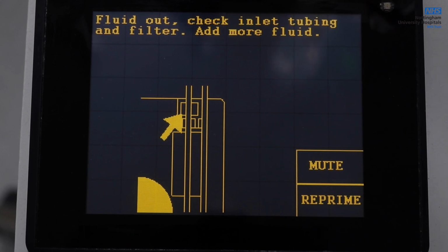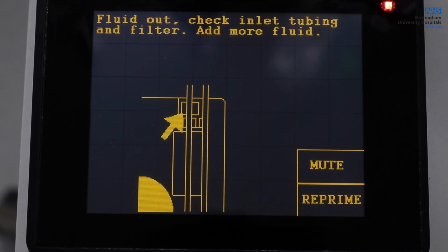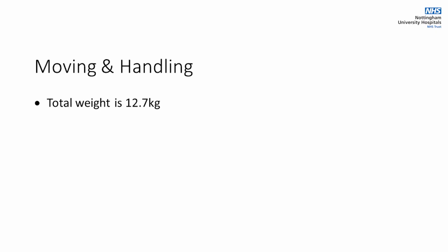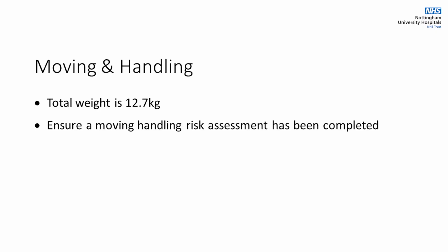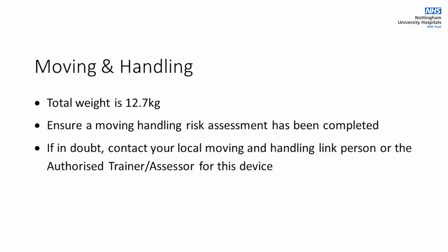How to respond to alarms and alerts on the device. The system will alert the user with an audible alarm if it senses a problem and will display instructions for corrective measures. To return to normal operation, follow the instructions. The total weight of this device is 12.7 kilograms. Ensure a moving and handling risk assessment has been completed if required. Consider task, individual, load, environment and stability. If in doubt regarding the moving and handling of this device, contact your local moving and handling link person or the authorized trainer assessor for this device.